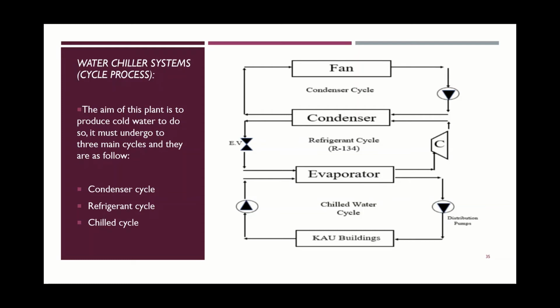Chiller removes heat from water by means of a refrigerant cycle, which is the second cycle. I am going to discuss it with you. It consists of condenser, expansion valve, evaporator, and compressor. A chilled water system refrigeration cycle works by removing heat from chilled water in the evaporator of the chiller. The compressor is what drives the entire process. It also uses the most energy in a chilled water system. In the condenser of the chiller, the heat is transferred to the condenser water. The liquid refrigerant goes through the expansion valve, also called throttle valve, where its pressure abruptly decreases.